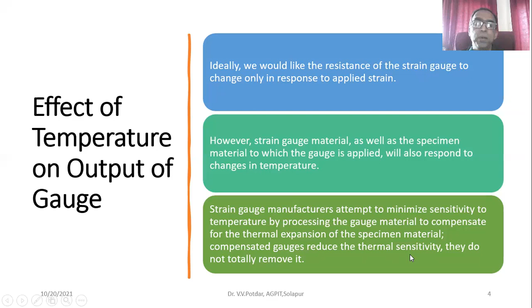Take a representative sketch. This is my active gauge, subjected to strain as well as temperature. This is the dummy gauge, which will be inactive to strain but active to temperature change. Here there will be delta R only because of T, and there delta R will be delta R because of epsilon plus delta R because of T. Because they are in subtractive mode, ultimately delta R because of T is eliminated, and what I get is purely resistance change because of strain alone. By using two gauges, one active and one dummy, the dummy is placed transverse to the applied strain, so strain has little effect on it.